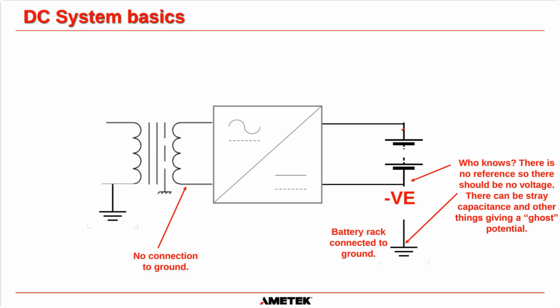If the battery did have some form of connection to ground, and let's say this negative was actually physically connected to ground, and they leaned on that battery rack, and let's say with their left hand, they've got their left hand on the battery rack and there was some exposed metal, and then they used their right hand to clean off a positive terminal on the battery without gloves on, obviously they should never do that, then they will be exposed to a shock in that circumstance. And we don't want that. We want our people working on the battery to be as safe as we possibly can. So that isolation transformer gives us that safety.